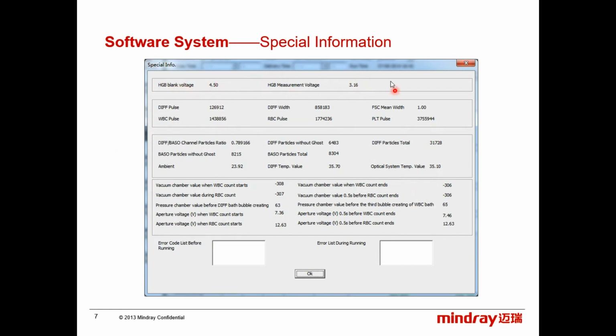Of course, the measurement voltage is always lower than the blank voltage, because here we have higher absorbance. All right. This is for the diff pulse. The diff width, the FSC mean width, WBC pulse, RBC pulse, and the platelet pulse. So here we have very important information: the diff baso channel particle ratio. Normally, this one theoretically should be as close as possible to 0.9. Okay, what does it mean?